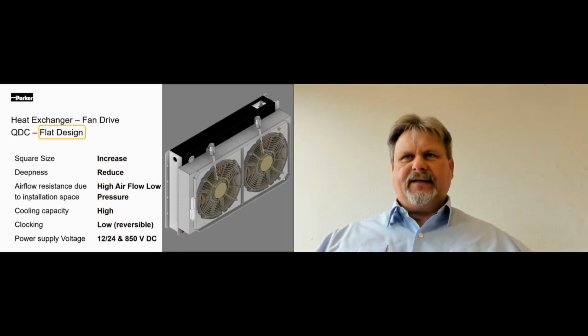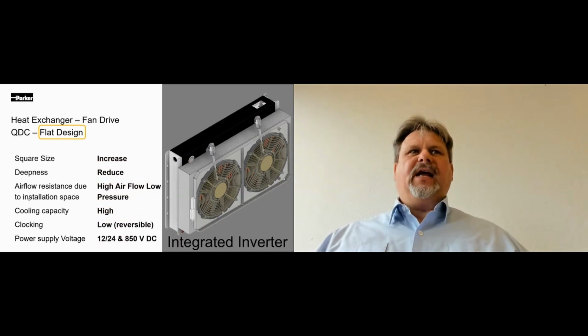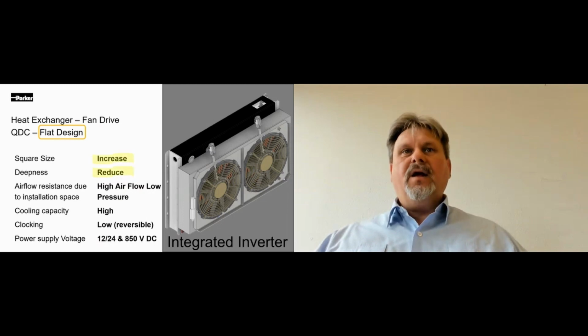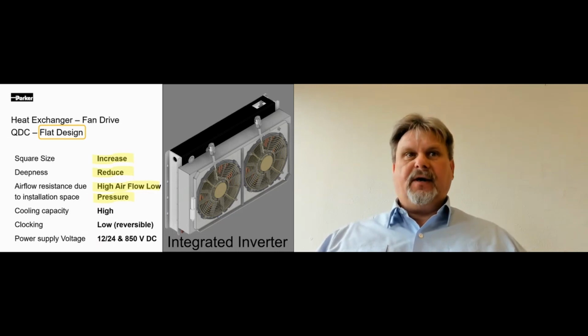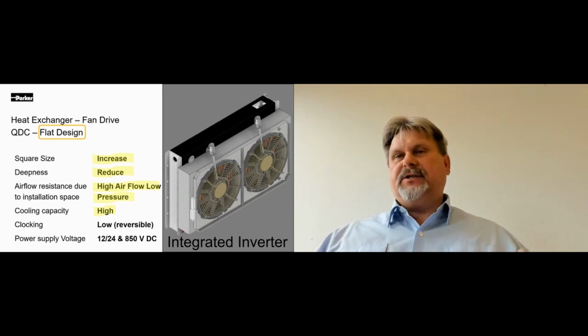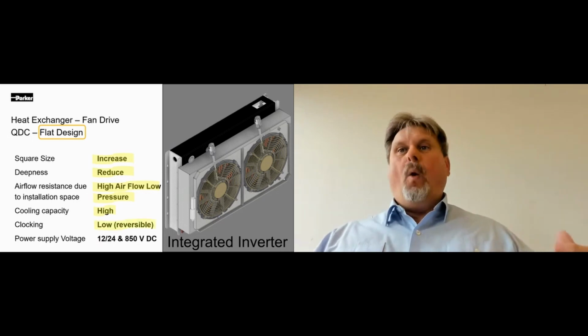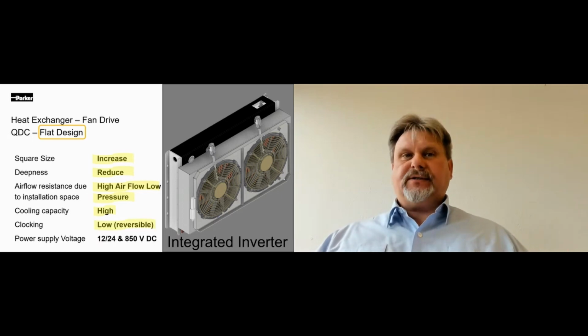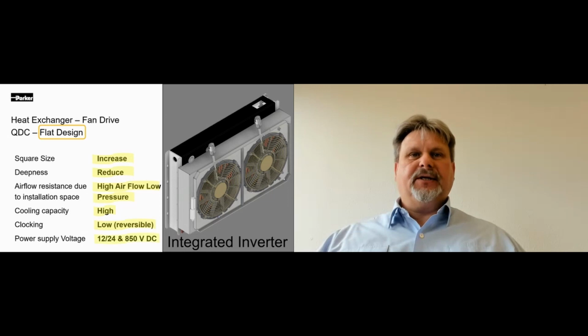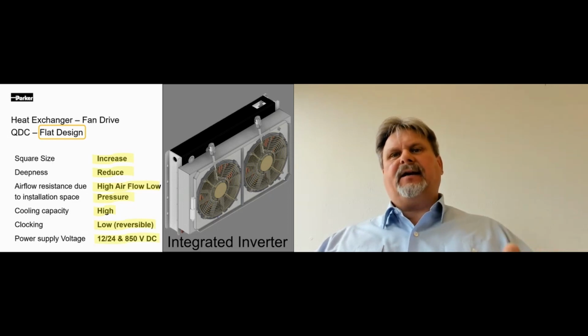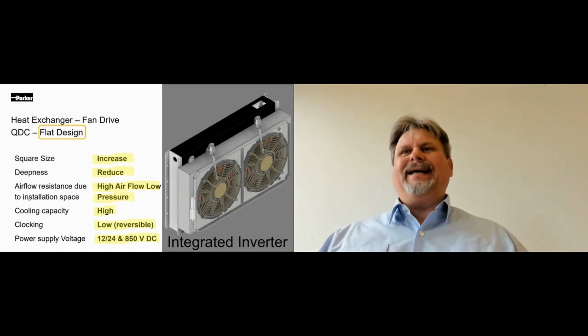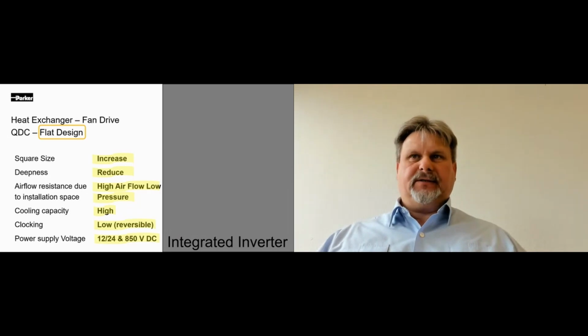Then we go to the flat design. The flat design has an increased square size and reduced depth, and has a very high airflow and pressure, not as high as the cube, but good enough in most applications. Cooling capacity with the new heat exchanger is quite good. The same, all the fans are built to do reverse spinning to clean the heat exchanger. What we provide here is a 12-volt solution, a 24-volt solution, and an 850-volt solution. And all of these have an integrated inverter so that you can use them directly with a PWM signal.